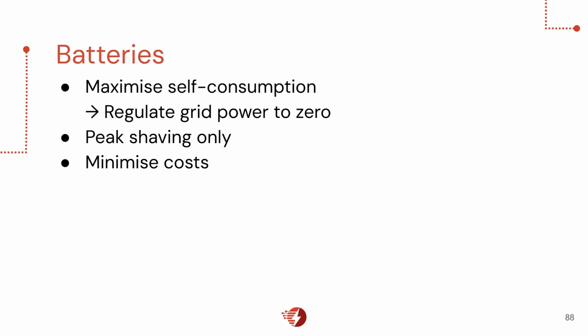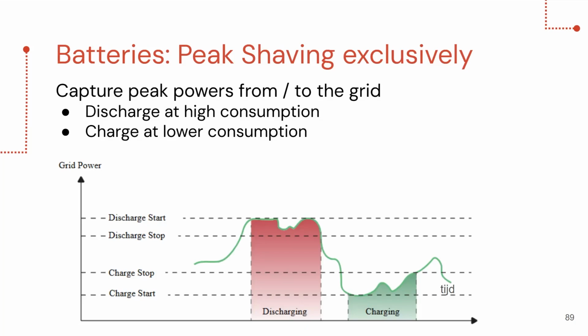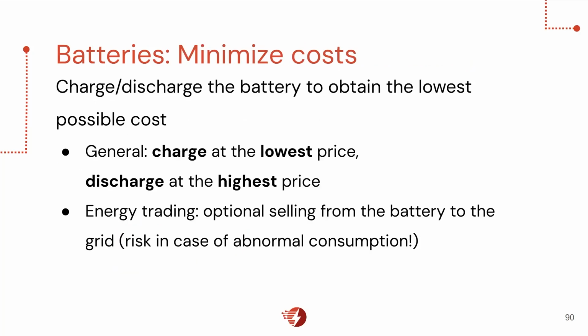To start with the batteries, we have a maximize self-consumption mode, which aims at zero on the meter - we always try to regulate it down to zero as closely as possible. Secondly, we have peak shaving exclusively enabled, which allows you to charge and discharge between certain values you set in the controller yourself. Then we have the minimize cost function, whose principle is to charge at the lowest price and discharge at the highest price.